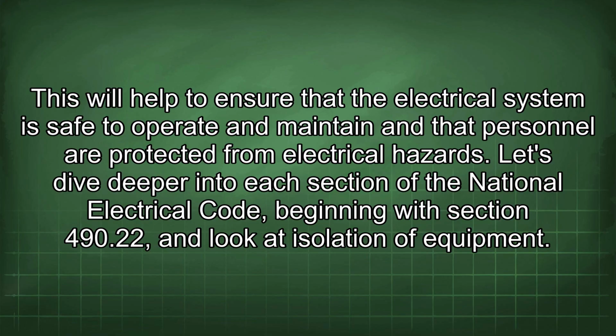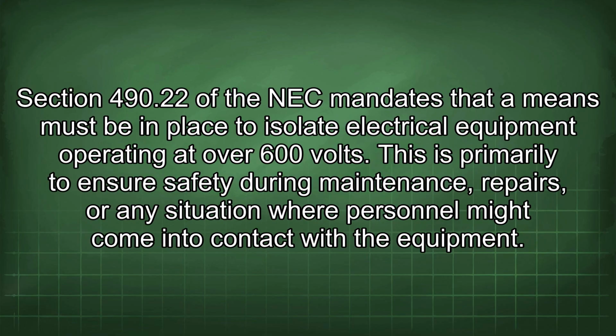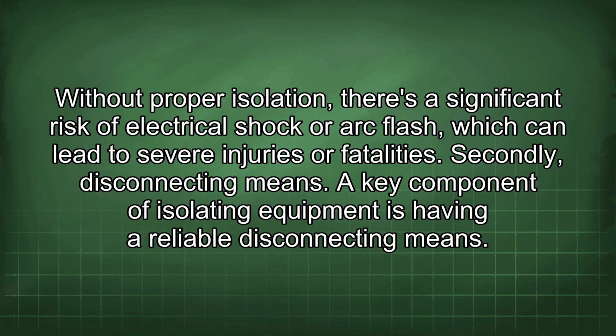Let's dive deeper into each section of the National Electrical Code, beginning with Section 490.22, and look at isolation of equipment. Section 490.22 of the NEC mandates that means must be in place to isolate electrical equipment operating at over 600 volts. This is primarily to ensure safety during maintenance, repairs, or any situation where personnel might come into contact with the equipment. Without proper isolation, there's a significant risk of electrical shock or arc flash, which can lead to severe injuries or fatalities.